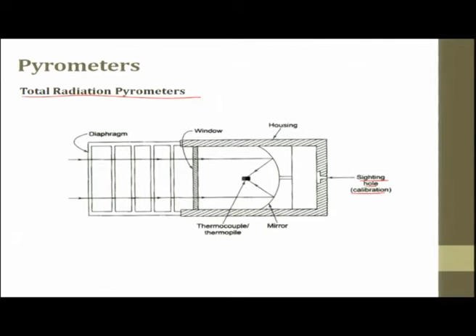So, this is how the total radiation pyrometer looks. This is the diaphragm, this is a window, and here is a housing. Here is a mirror which is polished very well. Here is a thermocouple and a hole through which you see and then you calibrate it. We adjust the diameter and then try to measure the temperature. The mirror type radiation pyrometer is shown in the figure. The diaphragm unit along with the mirror is used to focus the radiation on a thermocouple, and the distance between the mirror and the thermocouple is adjusted for proper focusing.